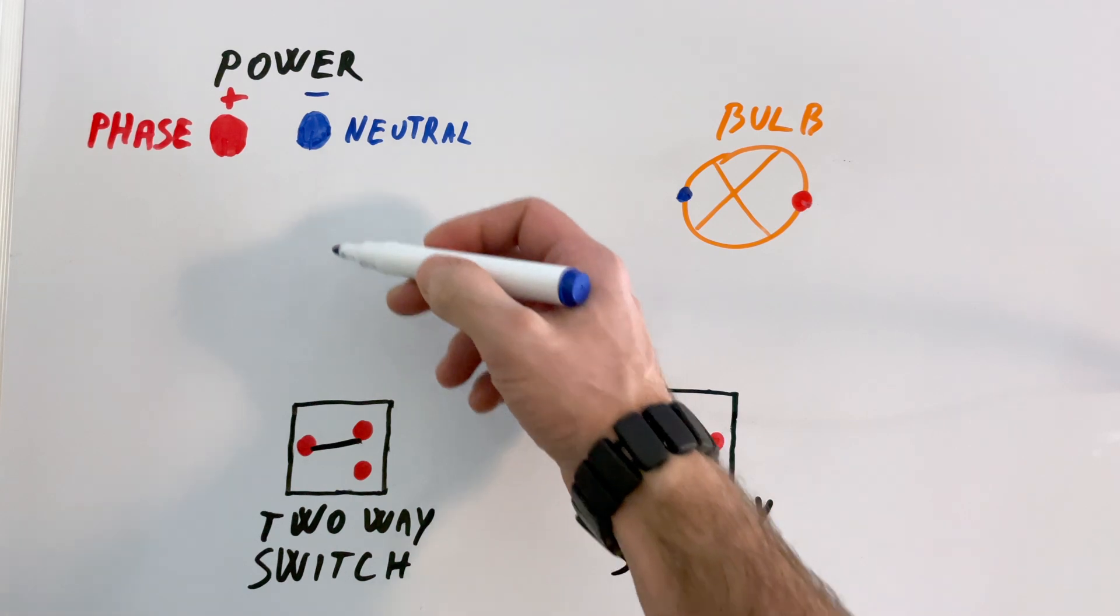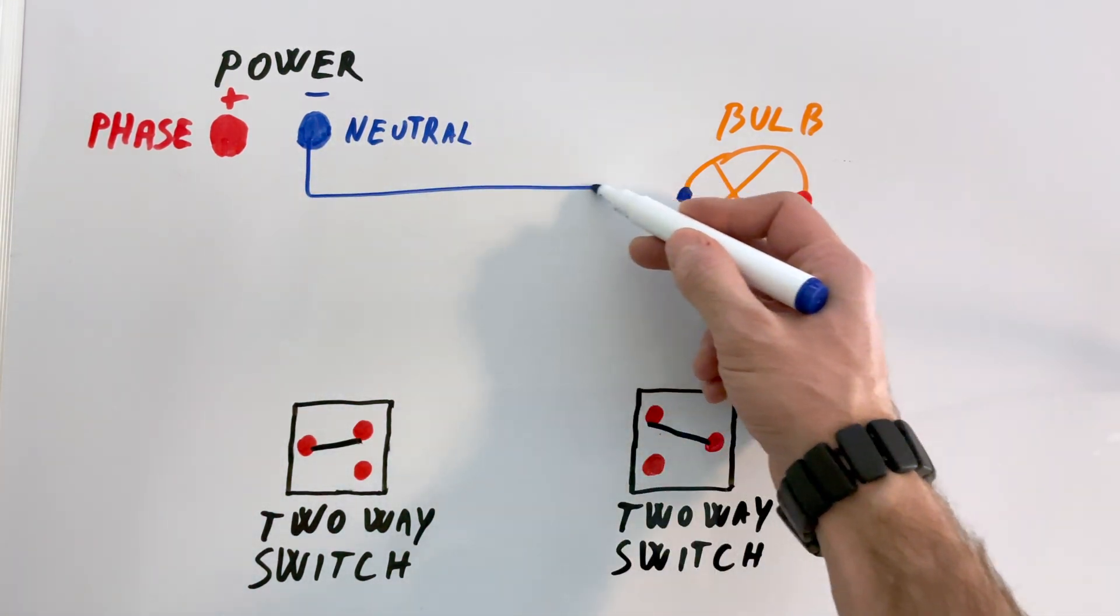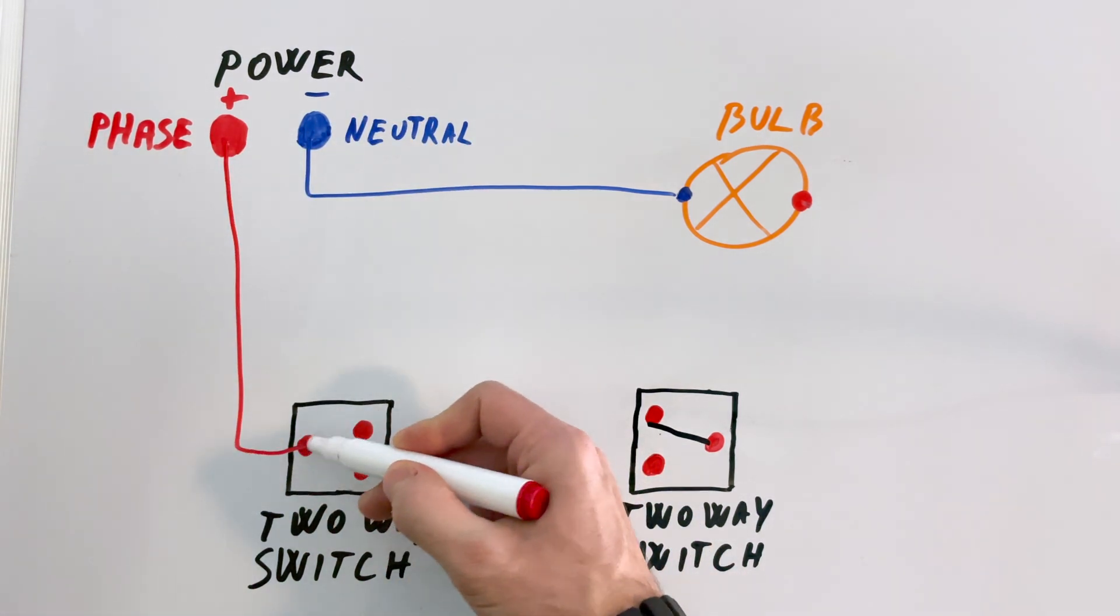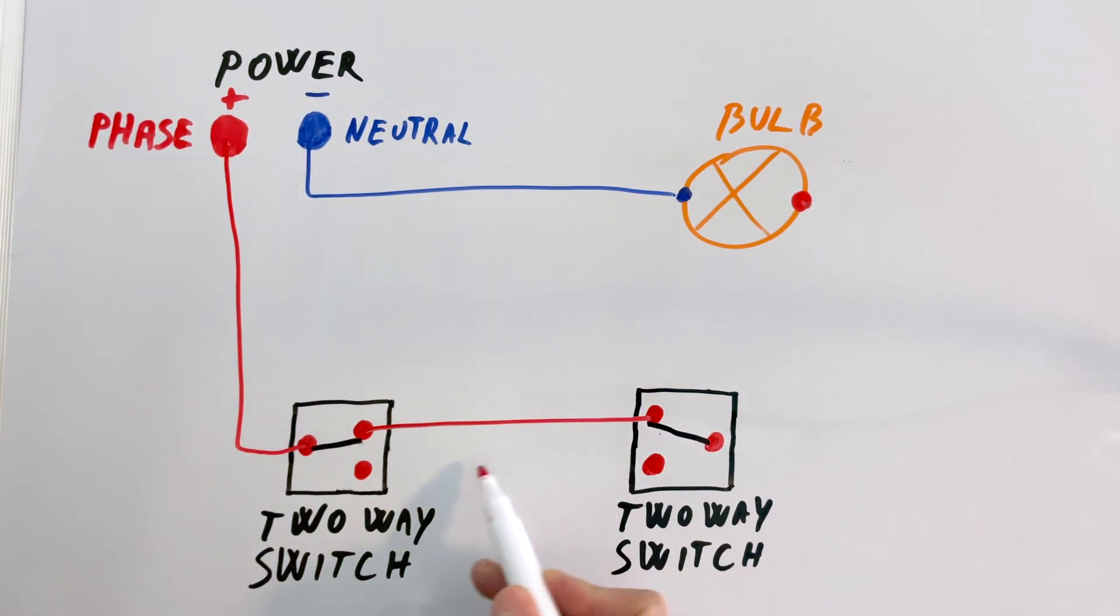First, the neutral wire goes directly to the bulb. The phase wire connects to the first switch. Then, we link the two switches together. Finally, we connect the common terminal of the second switch to the bulb.